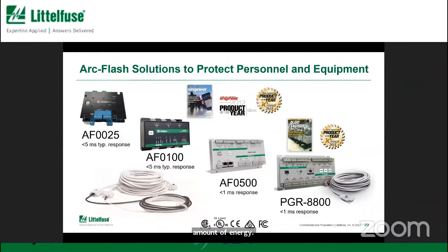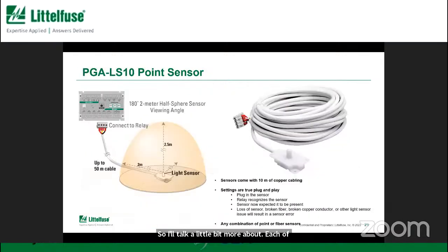So to talk a little bit about the Littelfuse arc flash relays that we have, there are 4 different models, but all of them operate on a very similar principle: looking for the light from an arc flash, reacting very quickly, and connecting that to a circuit breaker or an interrupting device that can clear the circuit. I'll talk a little bit more about each of them, but first, because they all use the same light sensor technology, I want to talk a little bit about that.